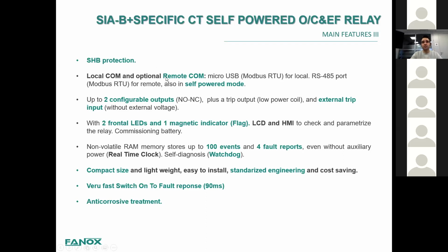It's important to note also that we have, of course, the local communication to make all the parameterization of the relay through a micro USB port with a Modbus RTU protocol, but also we have a remote communication that is available in self-power mode. I mean, you don't need auxiliary voltage, auxiliary power, to have this kind of communication. And it's becoming, again, more and more important because the SCADA system and the control systems require communications between all the points of the substation, of the farm. So again, it's important to have it in self-power mode.